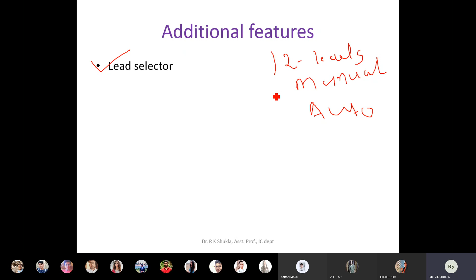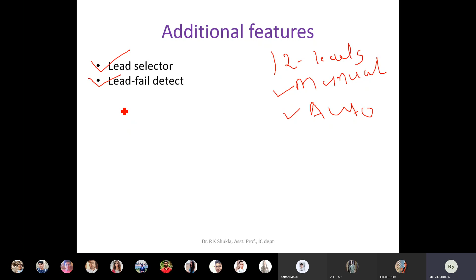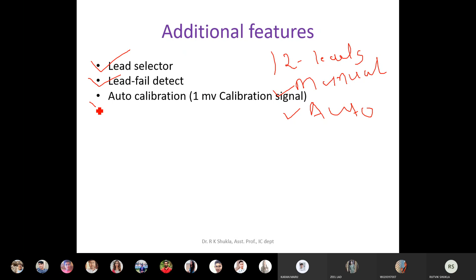Lead fail detect. So this is very, very important. If the signal which is taken by the electrodes from the patient to the machine, somehow if that lead has failed, if there is an interruption in the path of the signal from the patient to the machine, then that is also detected by the machine itself. Another feature is called auto calibration. Auto calibration means the machine itself calibrates by providing some standard signal.